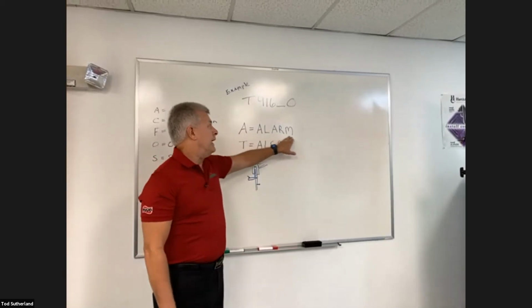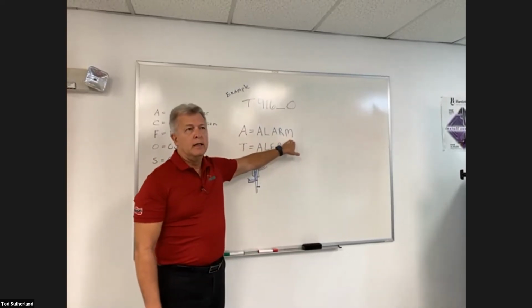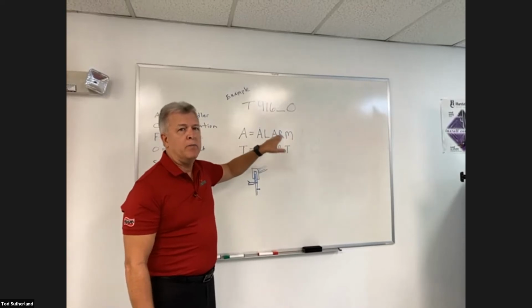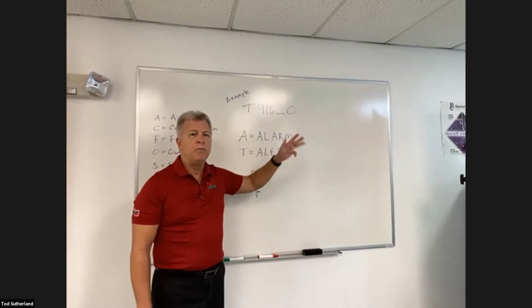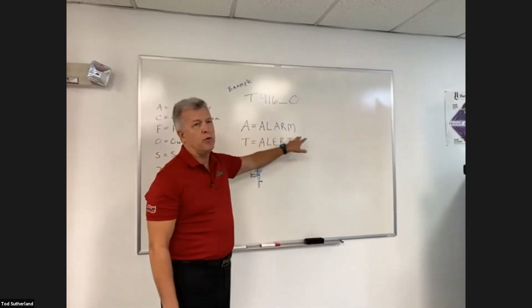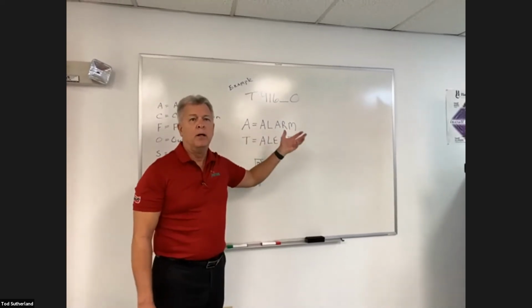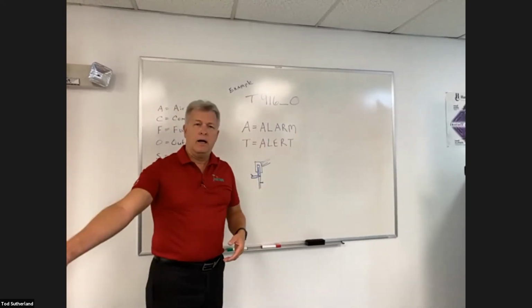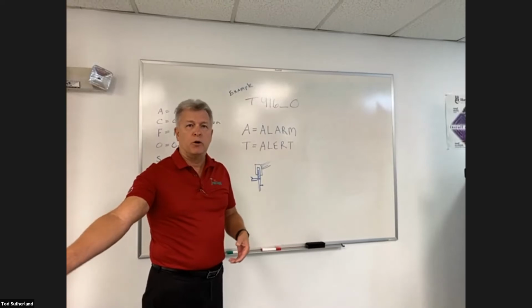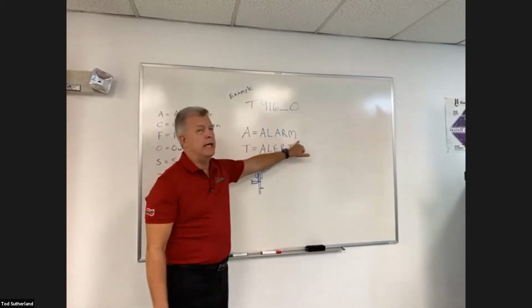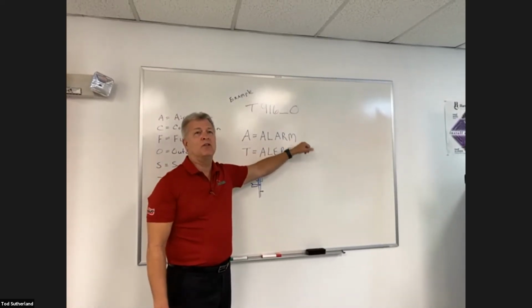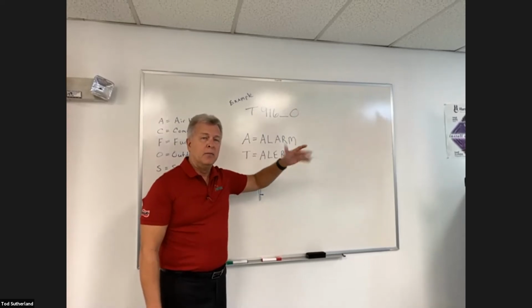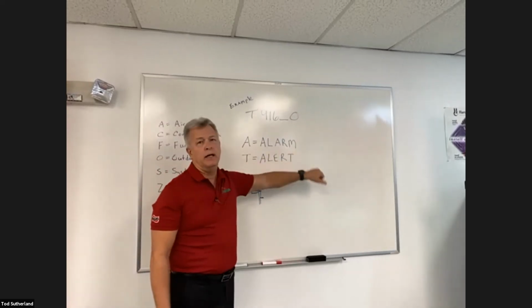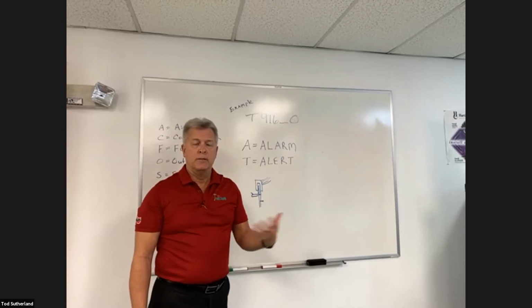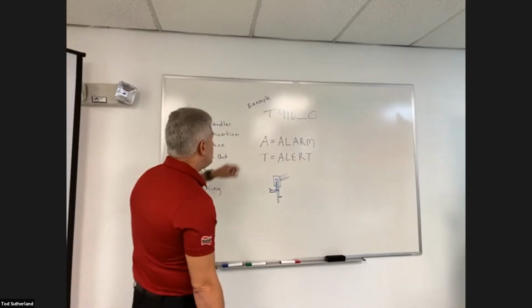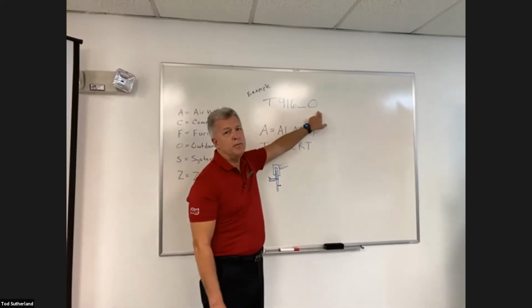An alarm, on the other hand, will take the system offline. It may not take it offline right away, but it may be like a 3 strikes you're out type of rule where it's going to try to continue to operate. But if it continues to get that same alarm 3 times within the course of a single call for cooling operation, it's more than likely going to take that system offline. It may even try to start the system up again later, but eventually an alarm will take the system offline and you'll have to figure out what the issue is and resolve it. This is an example of a code that you might see.